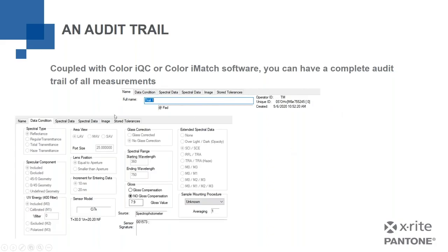I also can go and look at this data condition tab about my sample, my measurement, and see what kind of spectral was it. Oh, it was reflectance, or was it transmittance? What kind of specular component did I use? Was I filtering any of the UV energy? Which port size was used? Here, what sensor model? Ci7X, meaning it was a 7000, 7800, 7860, whatever. The sensor serial, even the serial number of the device. What wavelengths I was using. My spectral data. Even down here to the point where it records the temperature and the percent humidity.